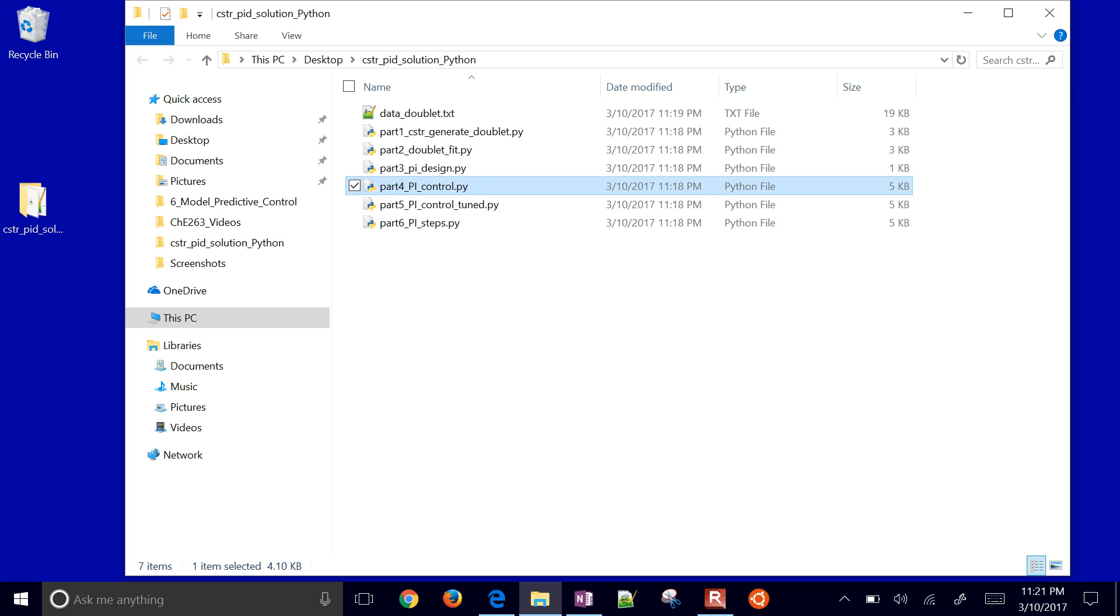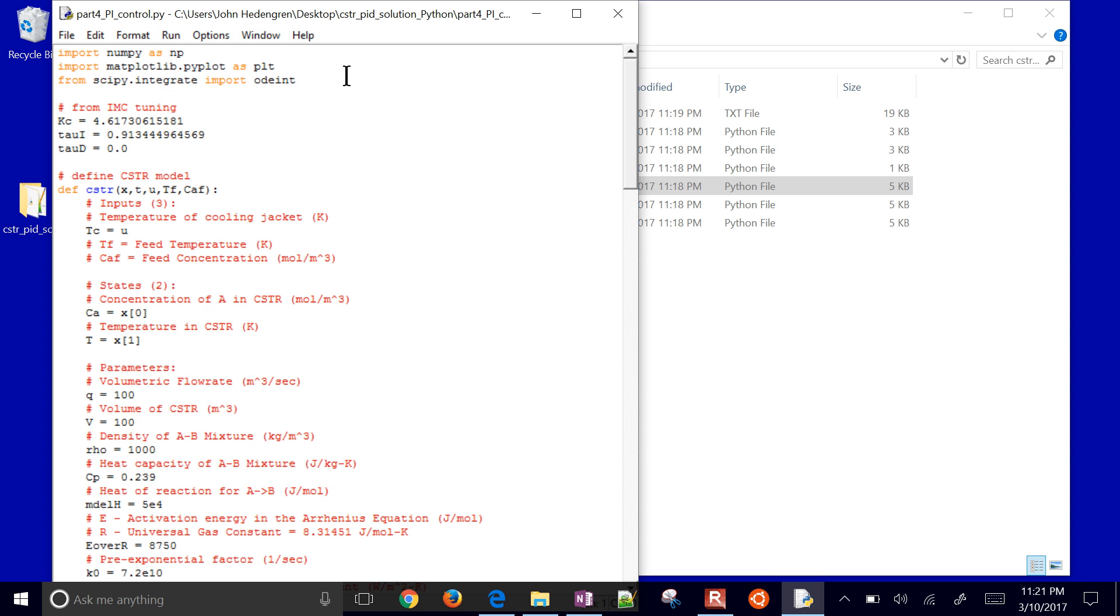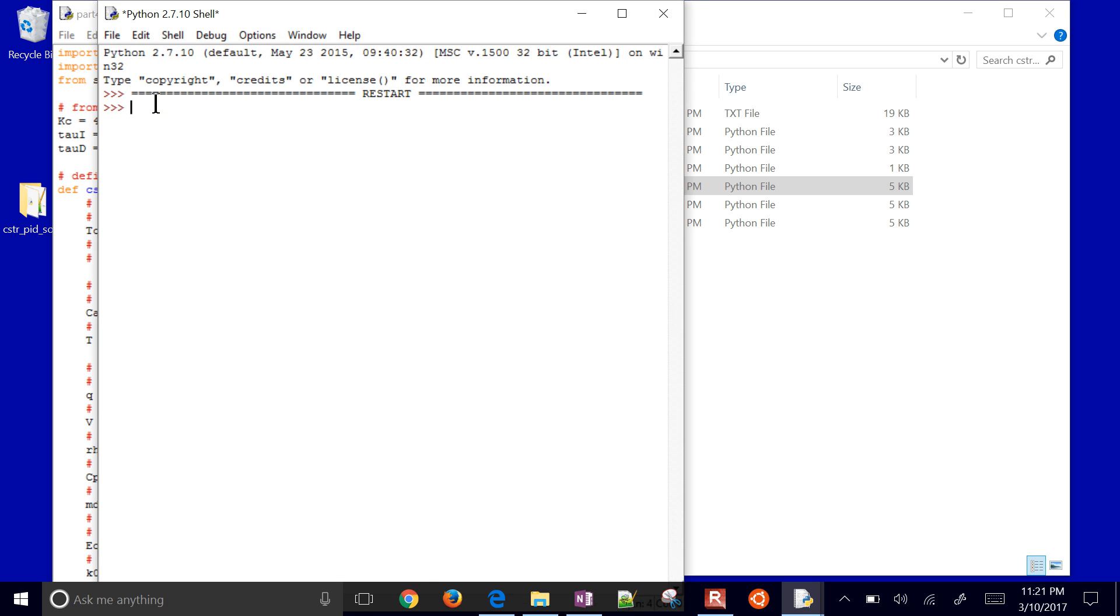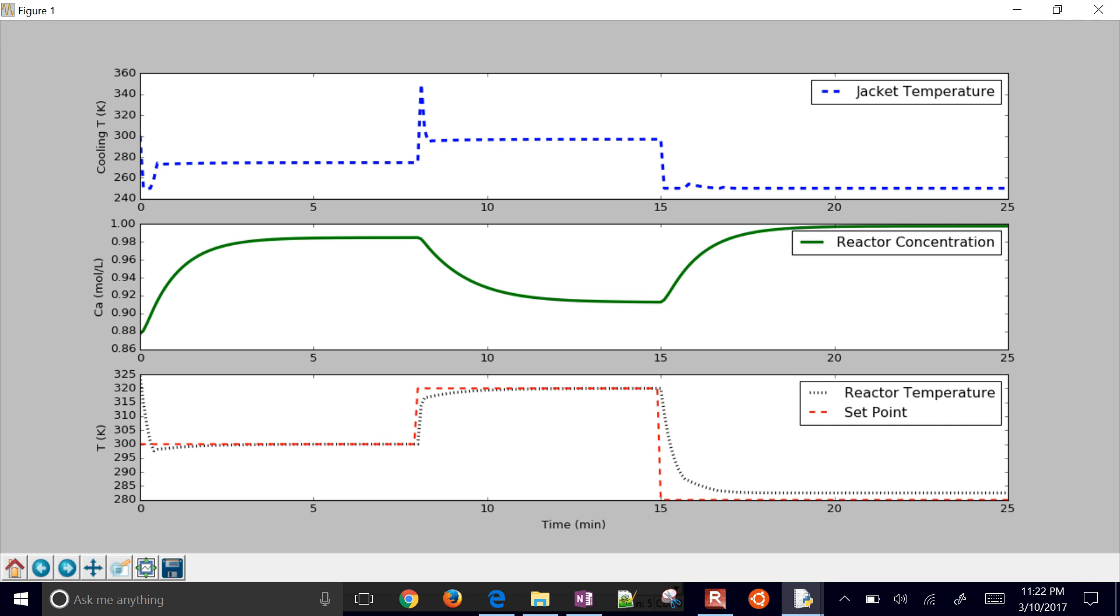Now we're going to go with the default ones, the ones that we just obtained from fitting that data. And this is going to implement a PID controller with the IMC tuning. And there we go. We have some set point changes. We started off at 300. We went up to 320 and then back down to 280.